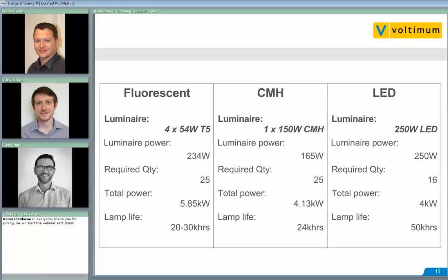The three light sources are fluorescent — a 4x54W T5 fitting at 234 watts total — ceramic metal halide, a single 150W lamp at 165 watts total — and LED, a 250W luminaire. Because of varying distributions and powers, the quantity required to light the room to 160 lux changes. Only 16 LED fittings are required, compared to 25 each of fluorescent and ceramic metal halide. This results in total powers of 5.85 kilowatts for fluorescent, 4 kilowatts for LED, and ceramic metal halide just behind LED.